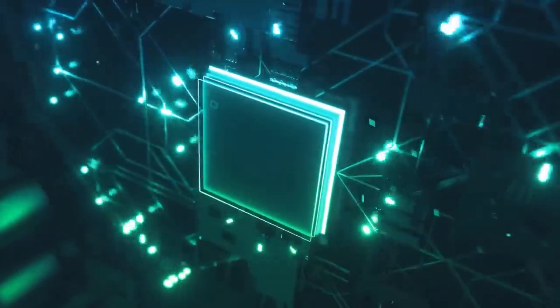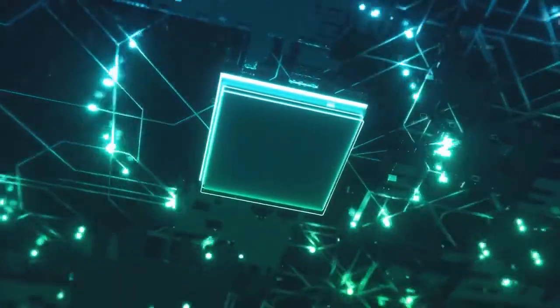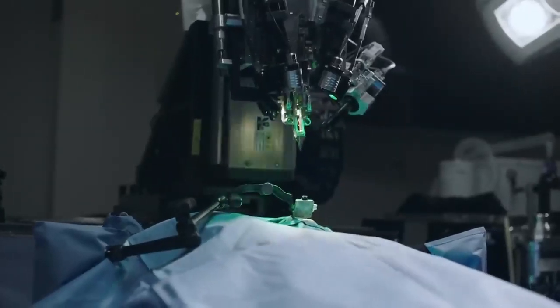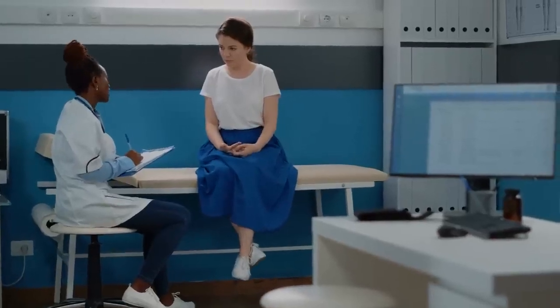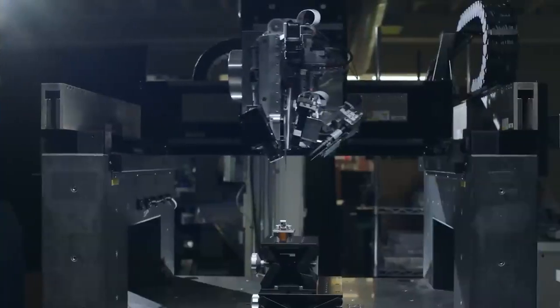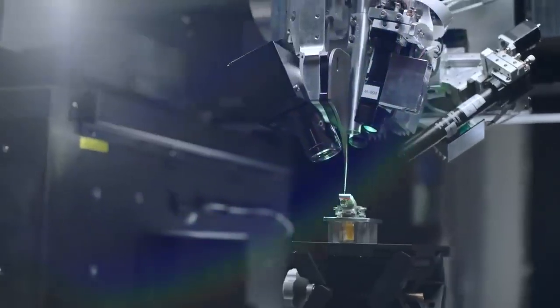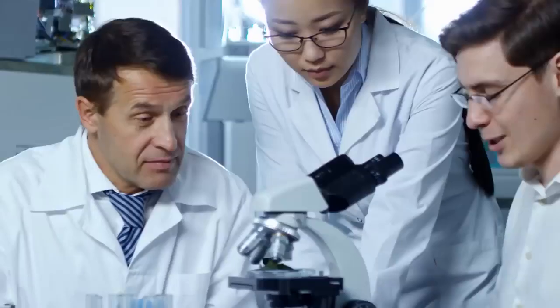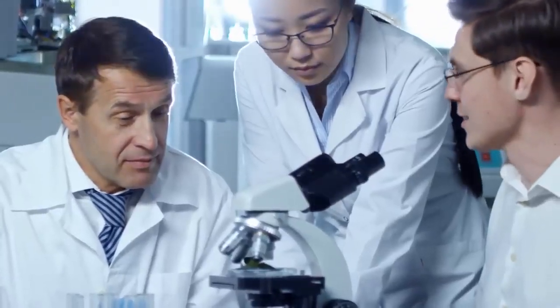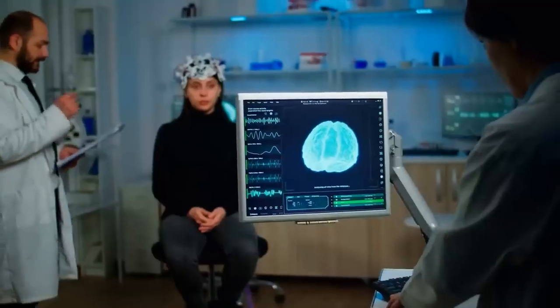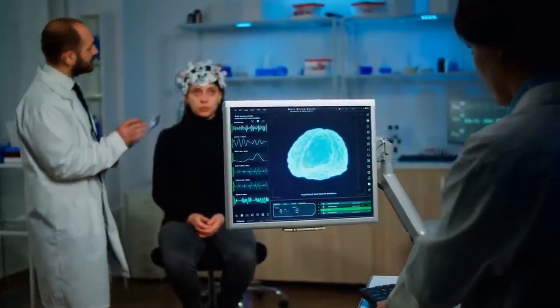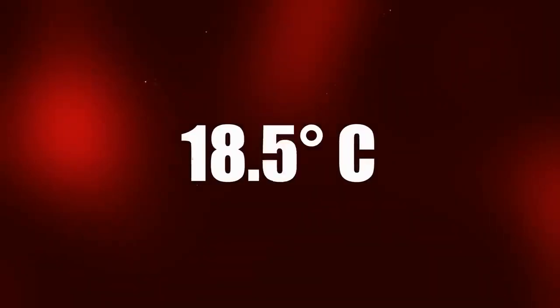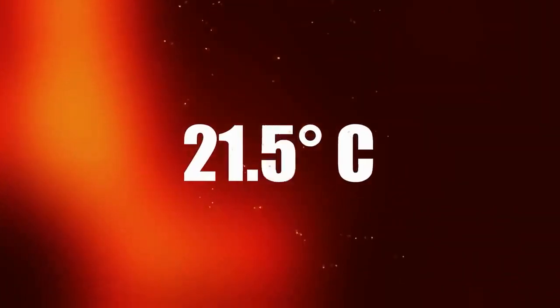By putting the implant device into this rig, they can get a minimum 4 times acceleration factor, so 1 month in the test rig would be the equivalent of at least 4 months in a live subject. And this way, they can stress test a device before it gets implanted. What they are looking for primarily is moisture entering the device. Designers are constantly monitoring the internal humidity of the implant. There will be a rise over time, but it should be very small and gradual. They also want to see how the battery and the systems are holding up over time.